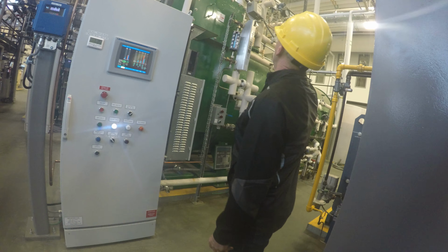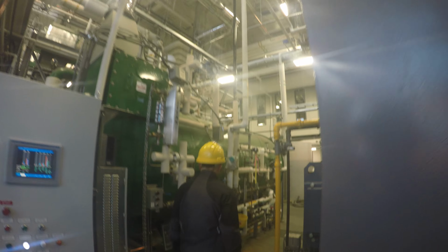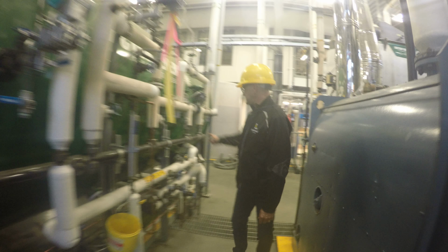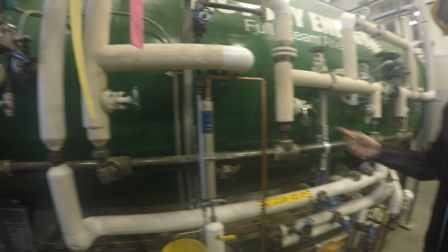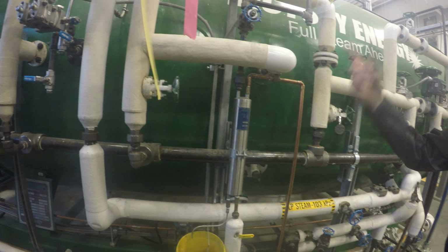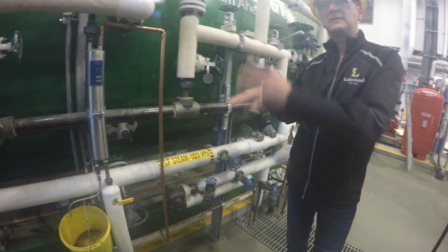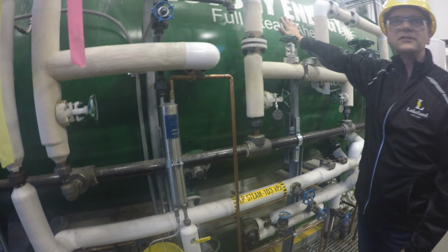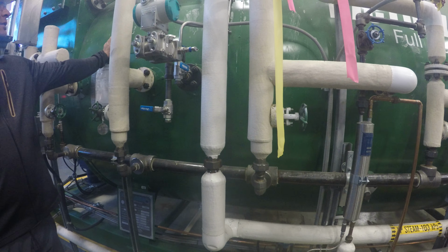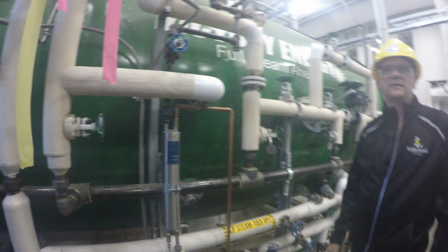Here's your water train. You can see where your water comes up into the condenser or the... This is low pressure steam coming in here. So inside the belly of this is a heating coil. There's a heating coil that loops back and forth, probably makes about 4 laps back in here. And this low pressure steam keeps her nice and warm. You put your hand on it, you can feel it's warm. So it stays warm all the time. So when you're ready to do your startup, it's good to go.